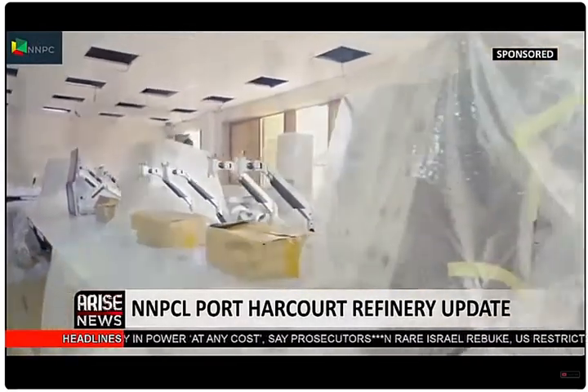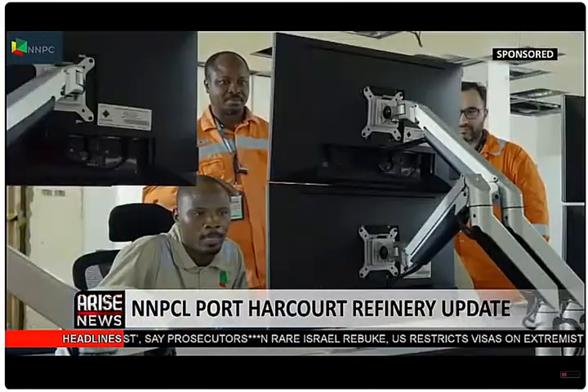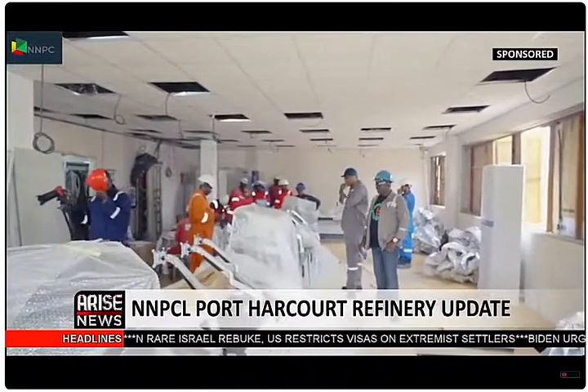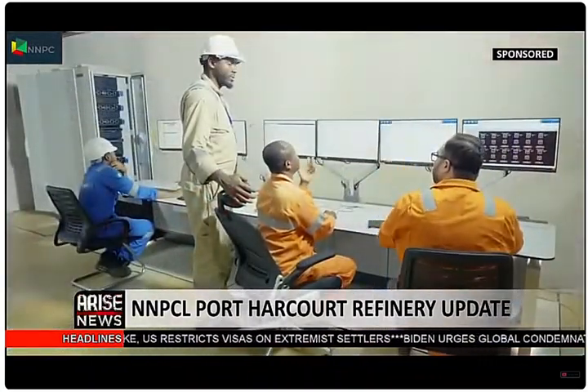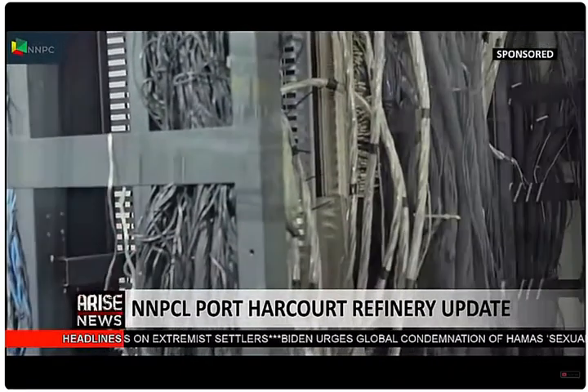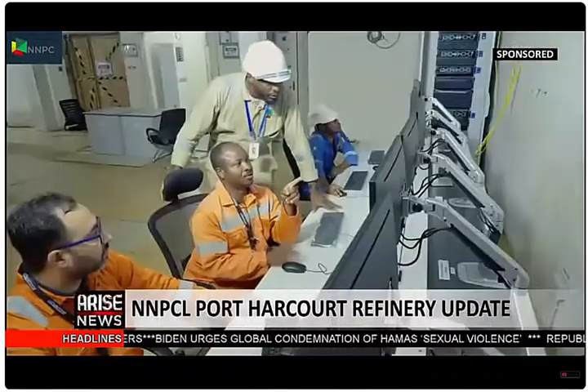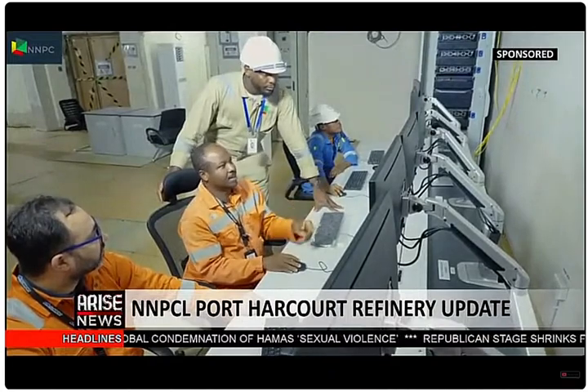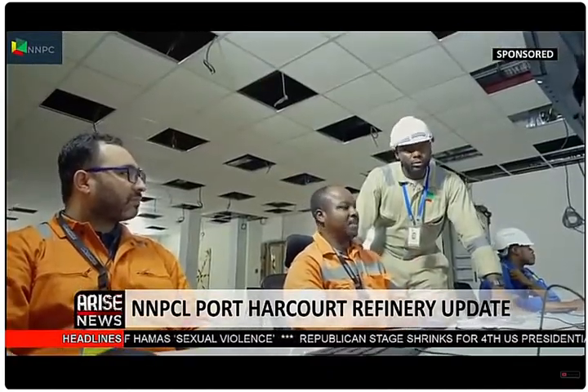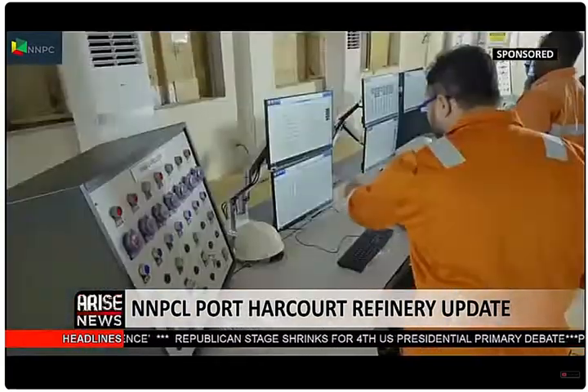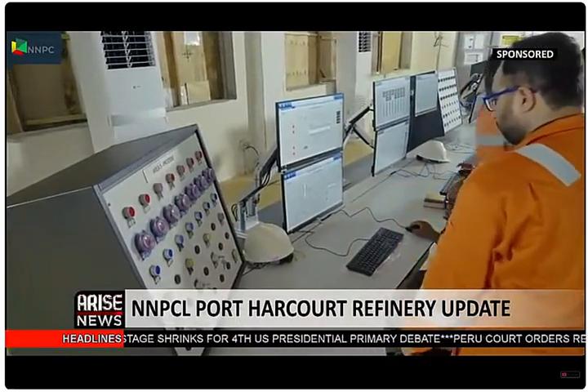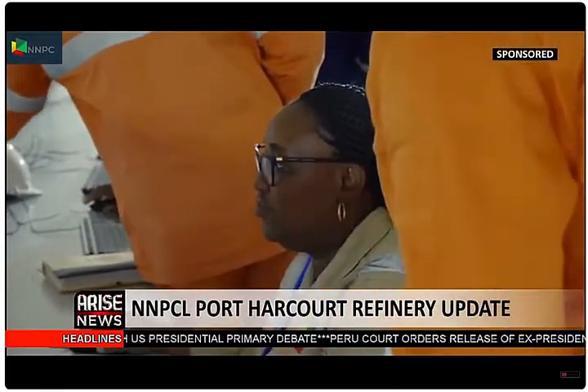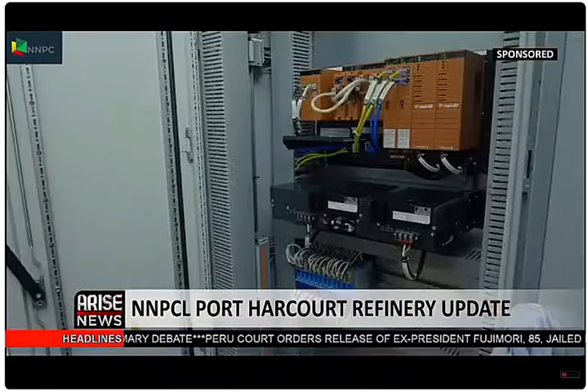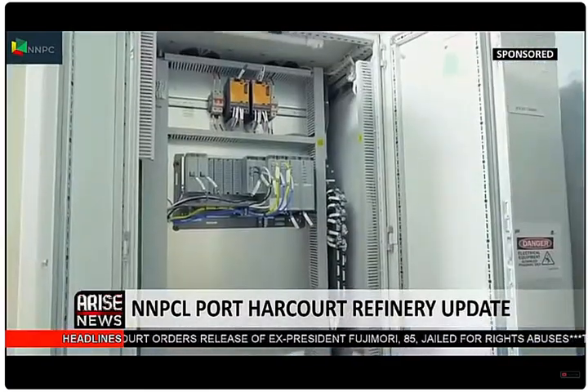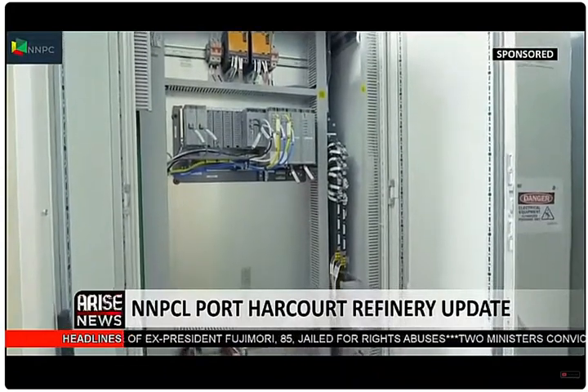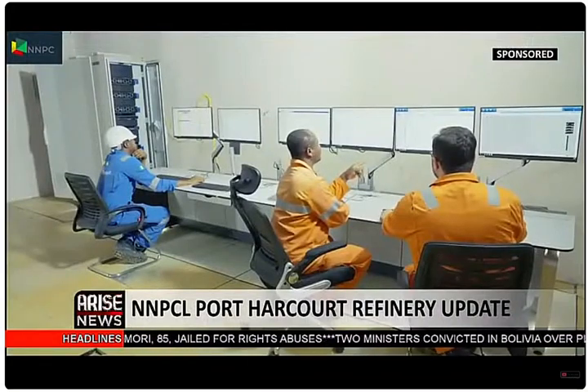The control room, which houses the integrated control and safety system, the brain of the refinery, comprising the distributed control system, the emergency shutdown system, and the fire and gas system, have also recorded remarkable progress in the past 2 weeks. It is in this room that the equipment which controls plant operations and monitors process conditions such as flow, temperature, and pressure can be found. The site acceptance tests for the Yokogawa Centum VP control systems, which involves the verification of the bill of materials, wiring corrections, layout drawings, general and internal arrangements of cabinets, and validating the functionality of the system, have all been concluded. Loop checking with field instrumentation is about to commence.